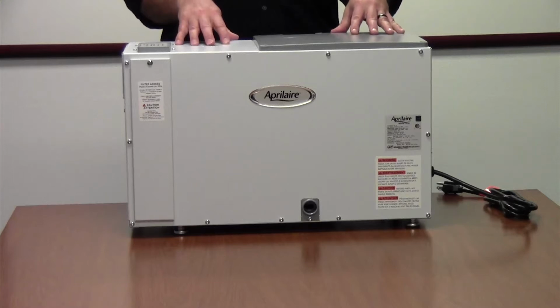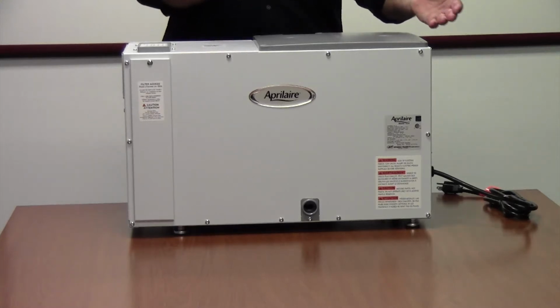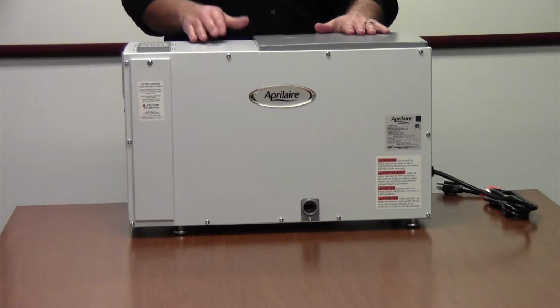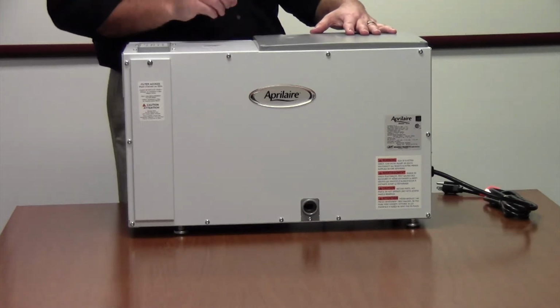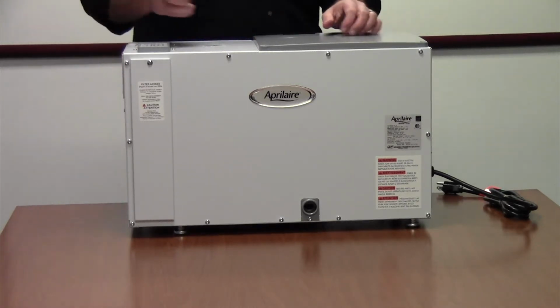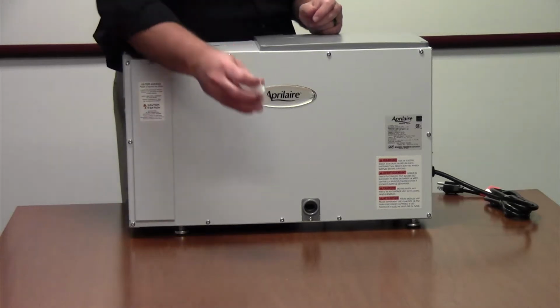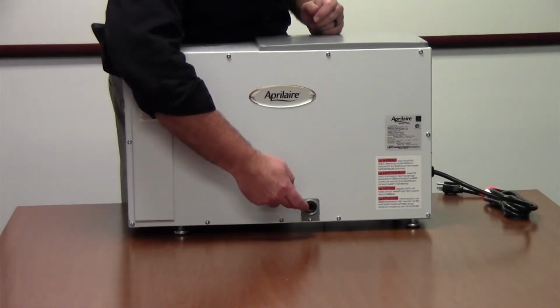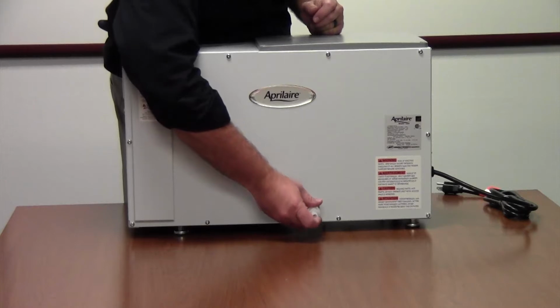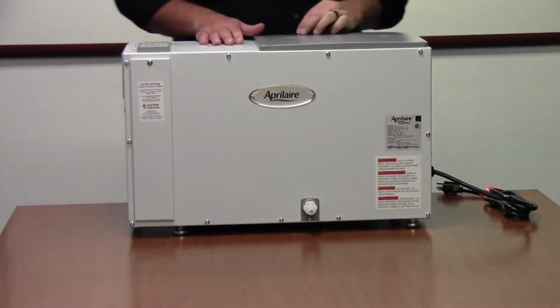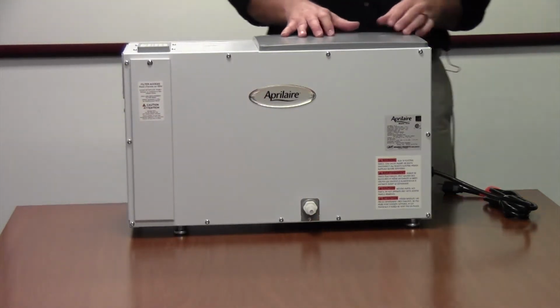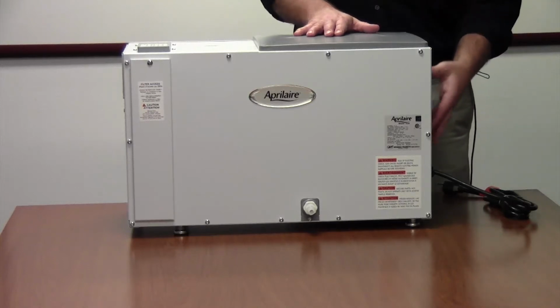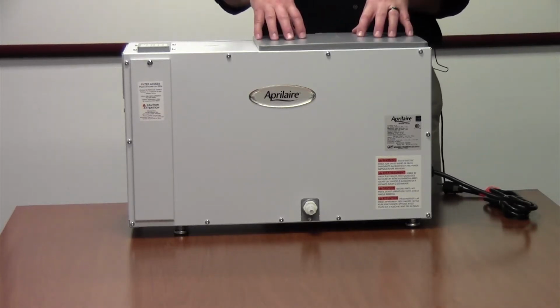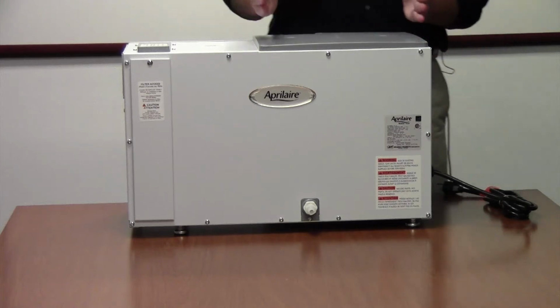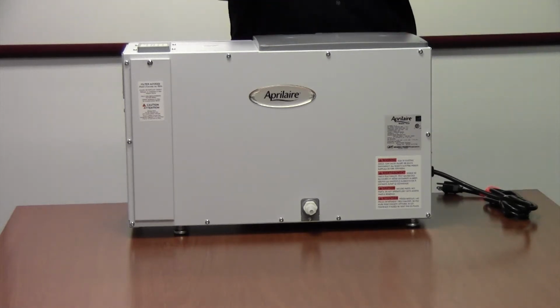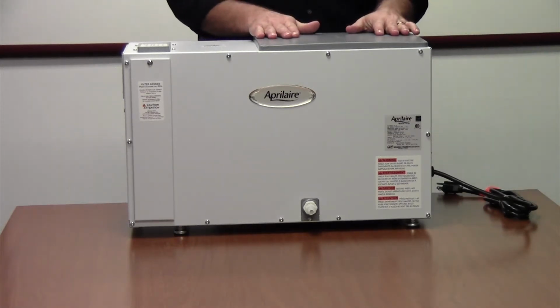One of the major changes to all the units going down the road is going to be a positive pressured cabinet. The positive pressure cabinet gives us a couple of things. It gives us the ability to remove the P-trap, no longer having a P-trap, and we can go directly with 3/4 inch PVC into the drain or use our adapter that we ship to take us down to vinyl tubing. It also allows us to discharge all the air out the back of the unit or out of the top. This plate can be taken off the top, moved to the back, and then you can have the discharge come out of the top if we're going up into the HVAC equipment.